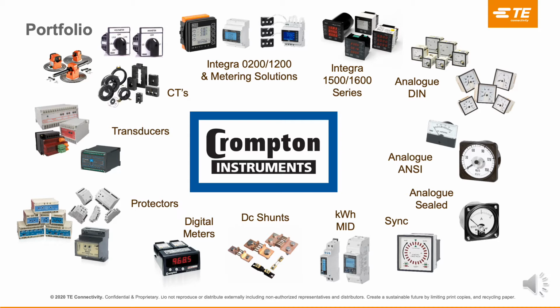Moving to the left hand bottom corner, we do a range of protection relays, which have a tripping function for amps, volts, frequency, phase balance, unbalance, synchro check, reverse power, earth leakage relay, and that's just to name a few. Old historical products, if I'm honest, is our transducer range. First started manufacture probably in the 1970s, but still has a large outcome in the market with most outputs like 4 to 20 milliamp, 0 to 10 volts, and this is converted from AC and DC power measurement from currents, kilowatts, watts, VARs, VA, power factor, and basically transduces the input to a DC output, which is more manageable in relation to the range.